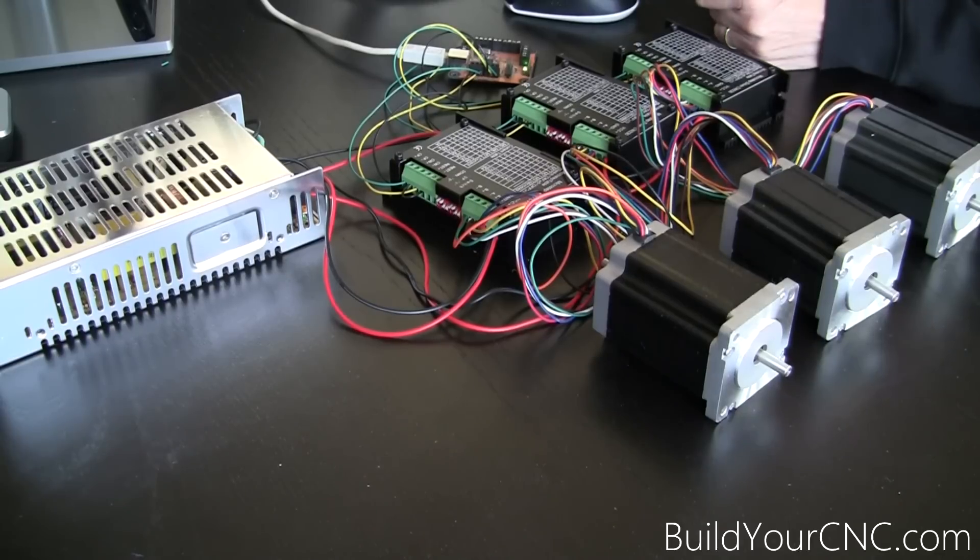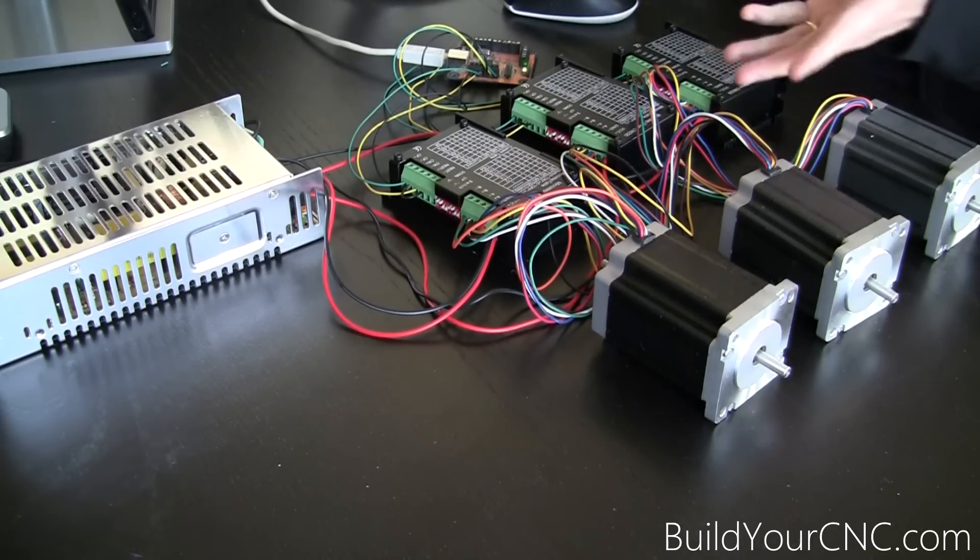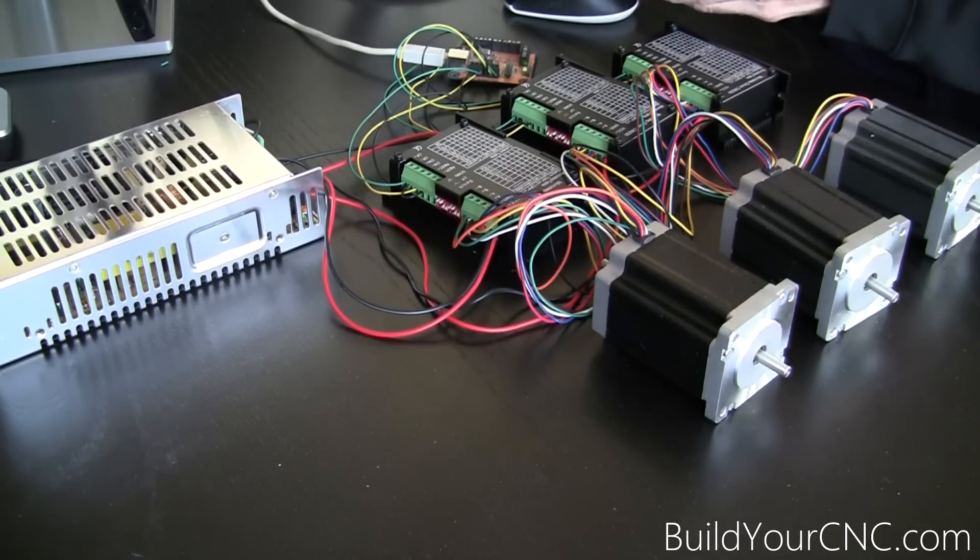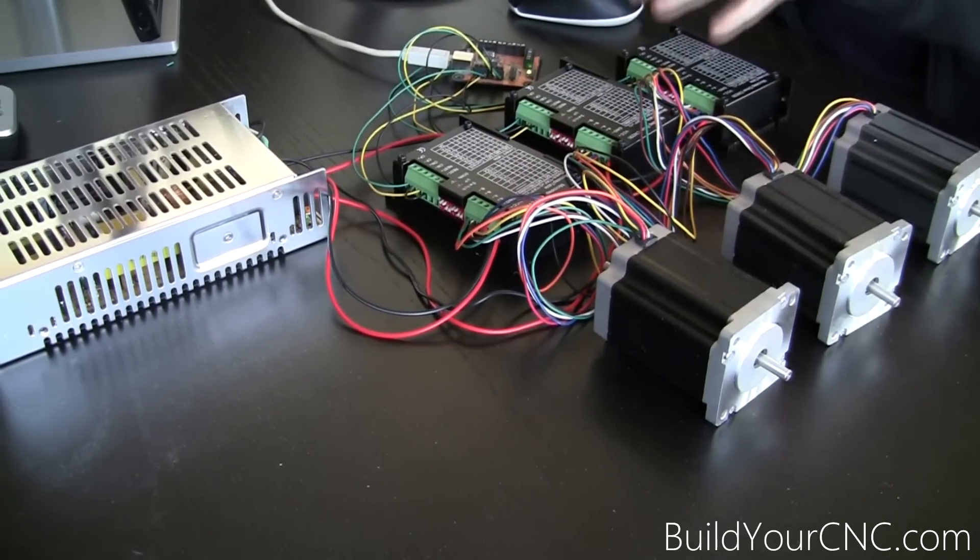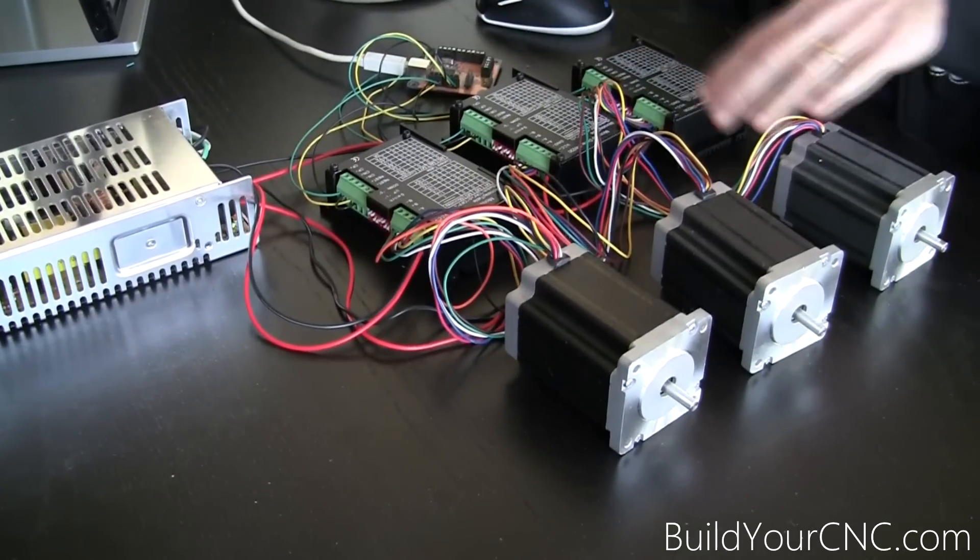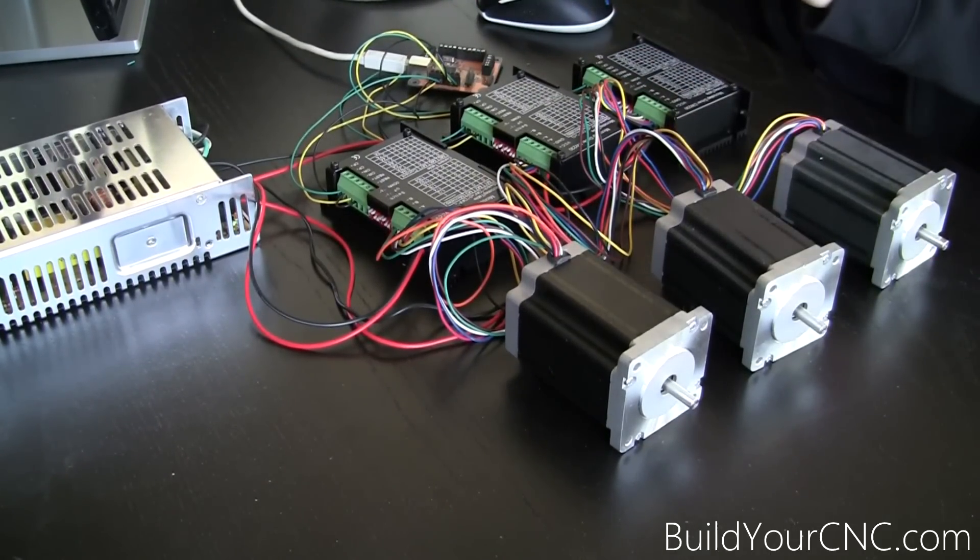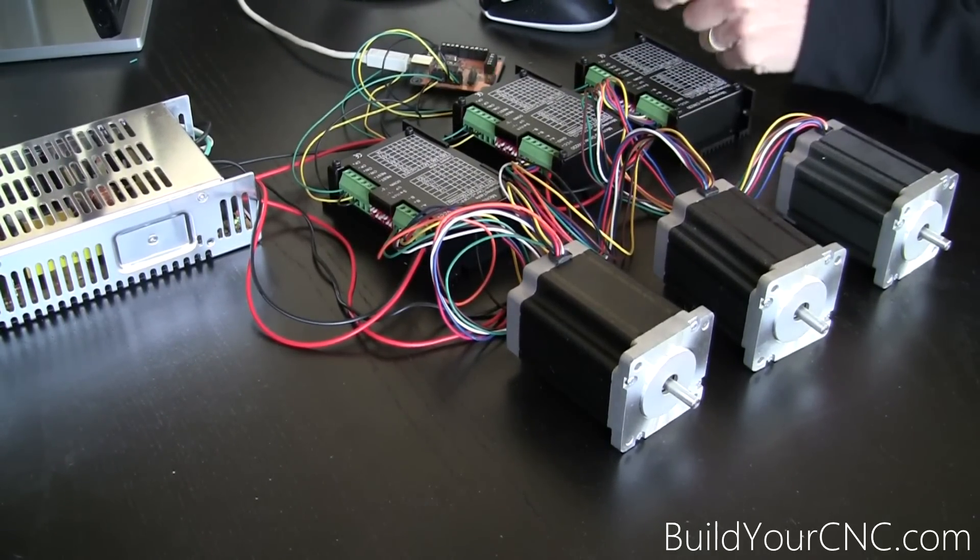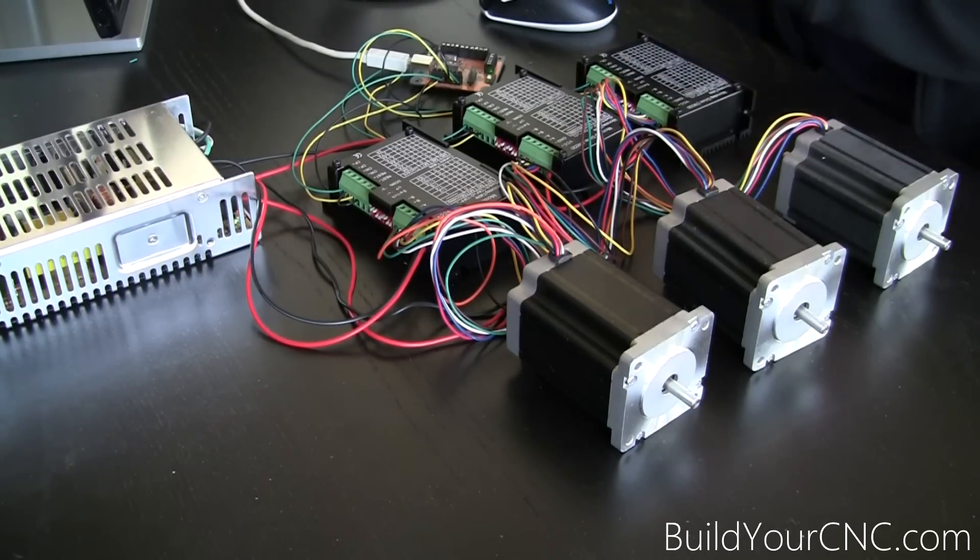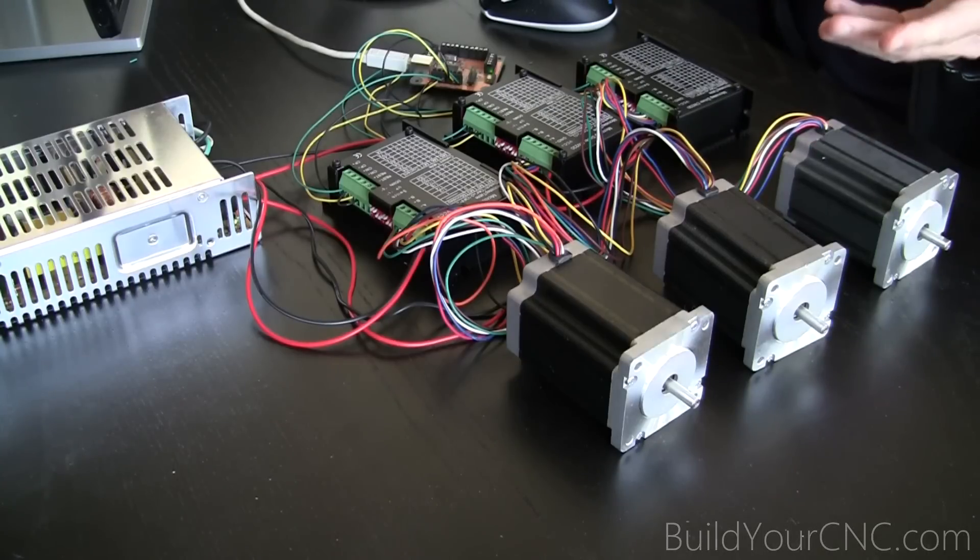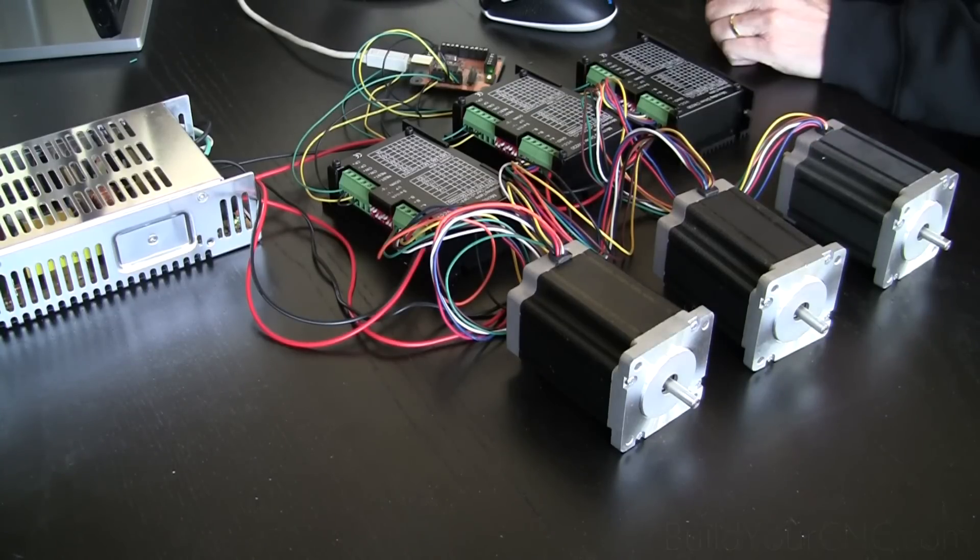Ensuring that each driver and motor set works before we go to the next driver will help you in troubleshooting if one driver or one motor isn't working for some reason. You can troubleshoot that much easier than if you had all of them connected at one time, trying to get them all to work after you've connected all the wires and everything. So if you start with the fewest variables, the simplest method, just working with one driver at a time, making sure that those work, you have minimal wires that you have to understand and deal with when you're doing the troubleshooting. I hope that helps. Thank you for watching.